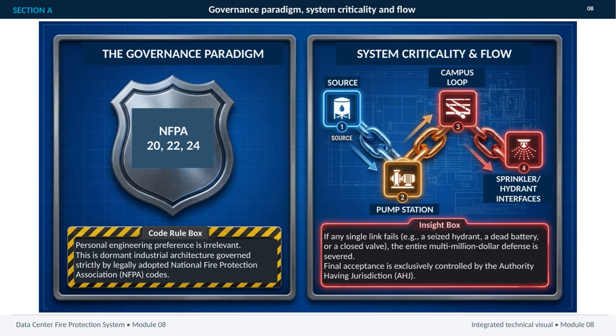The system is dormant industrial architecture, meaning it may sit unused for long periods, but it must perform immediately and reliably when demanded. Its design and acceptance are governed by legally adopted National Fire Protection Association standards, specifically NFPA 20, NFPA 22, and NFPA 24. The flow begins at the source, moves through the campus loop and pump station, and then reaches the sprinkler and hydrant interfaces. Each stage is part of one connected defense, not an independent feature.